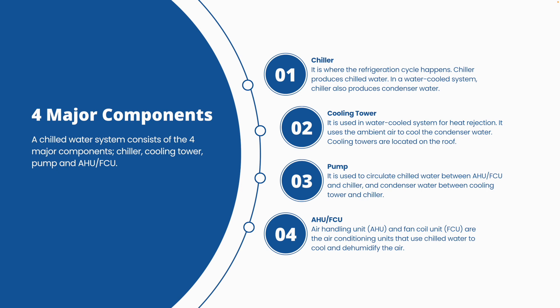The third component is the pump, which is necessary to move water around. We have two sets of pumps: the chilled water pump and the condenser water pump. The fourth component is the AHU and FCU — air handling unit and fan coil unit. These are the air conditioning units that cool down the room air, using chilled water instead of refrigerant to cool down and dehumidify the air.